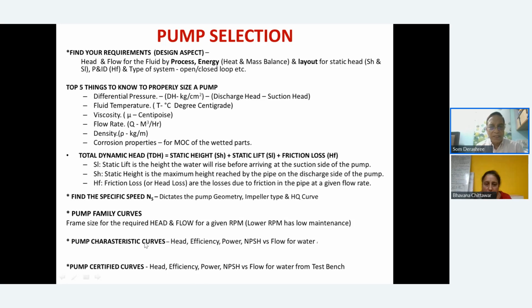Then you have to know the pump characteristic curves, which give you the head, efficiency, power, NPSH, net positive suction head, which we'll dwell on in detail, and the flow of the water. And then the pump certified curve. What is the pump certified curve? At the design stage, you normally ask for pump certified curves. These are curves given for a particular pump on the test bench by a manufacturer. The default is water, because he is going to use only water, but your application may be some solvents or something else. Now you will have to do the corrections. We'll share details on the corrections required in the subsequent slides.